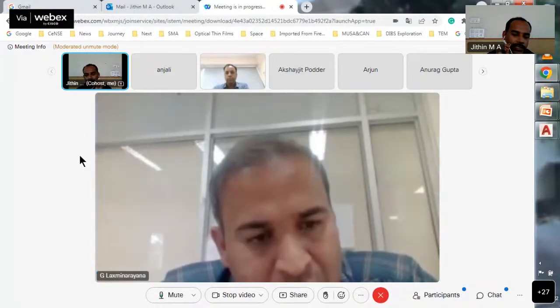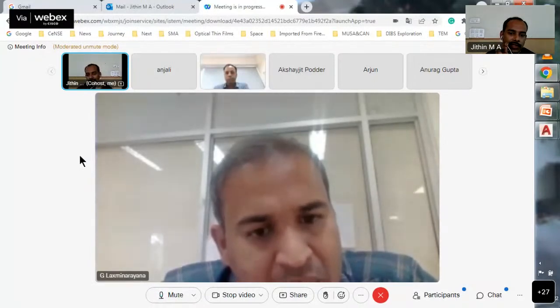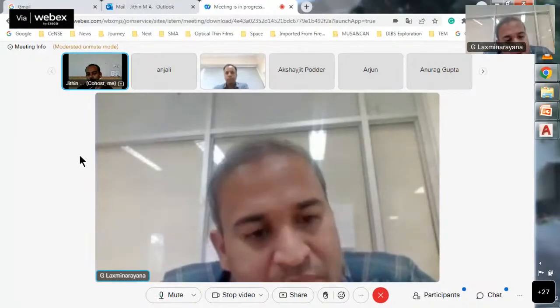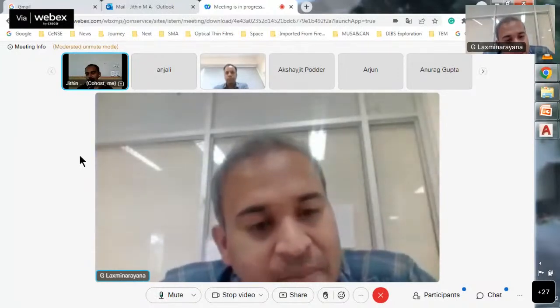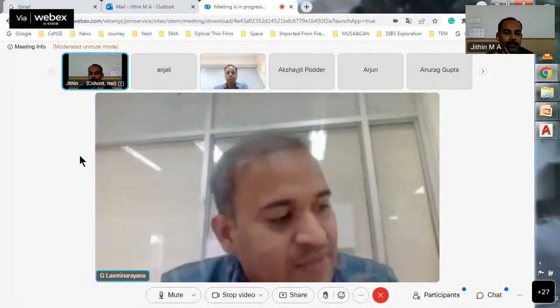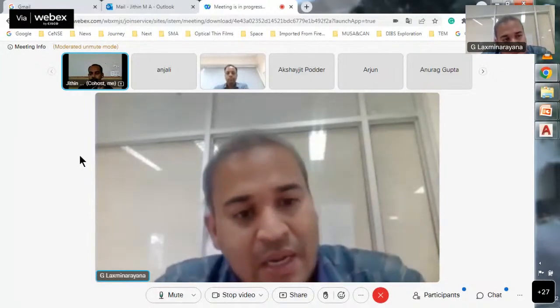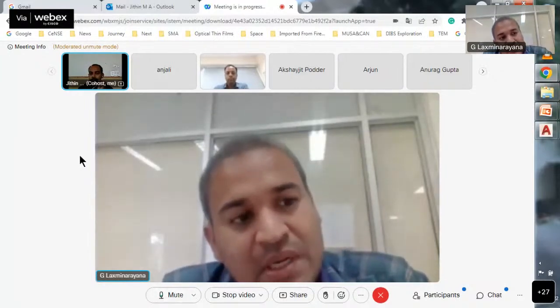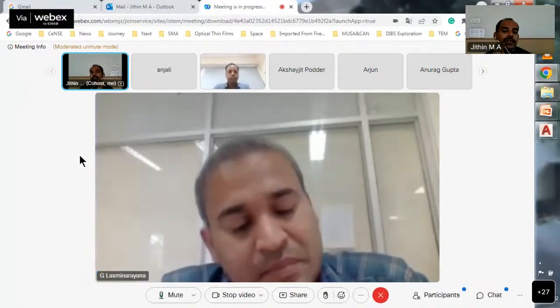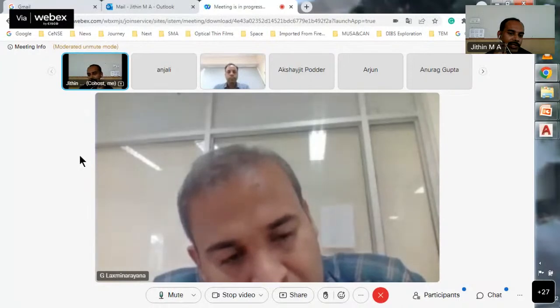That is again a different topic. I didn't share that slide here because it is a different topic. That is called rate of rise. You can also think of rate of rise as a leak rate. Let us say there is a leak which causes a rise in the pressure, ignoring outgassing effects for the time being. How to correlate this value to the machine displayed leak rate? We cannot say that, because in a leak test we can see only helium gas.